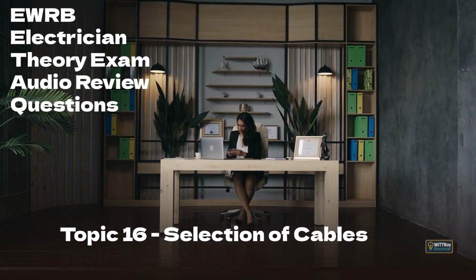Higher ambient temperature leaves less cooling margin. The conductor reaches its maximum temperature at a lower current, so derating is required. Review question 24. Why is mechanical protection part of cable selection?